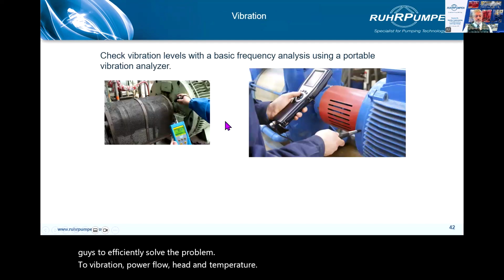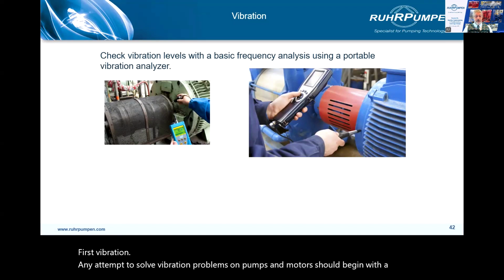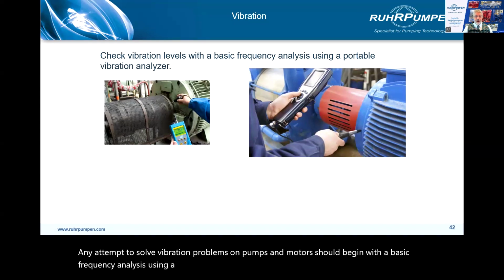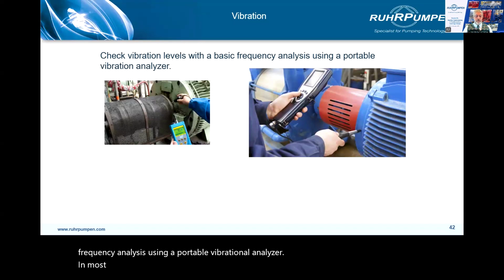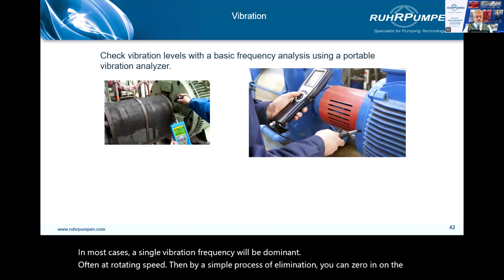First, vibration. Any attempt to solve vibration problems on pumps and motors should begin with a basic frequency analysis using a portable vibration analyzer. In most cases, a single vibration frequency will be dominant, often at rotating speed. Then, by a simple process of elimination, you can zero in on the source of the problem.